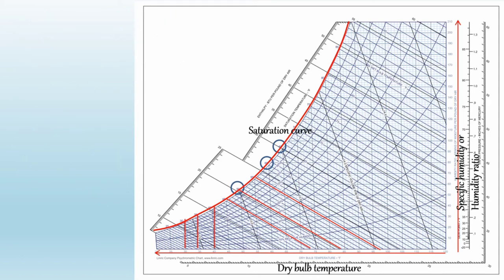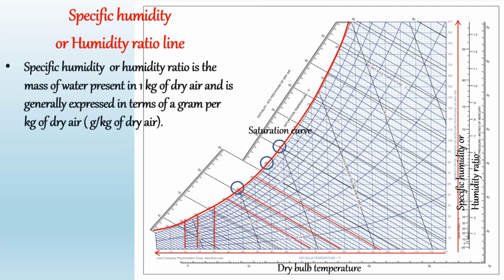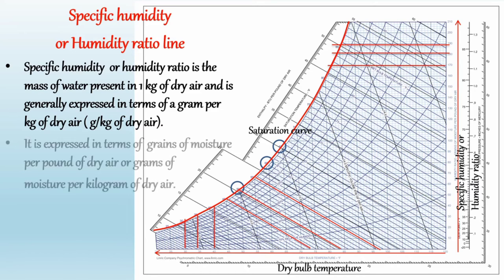The next line is the specific humidity or humidity ratio line. Humidity ratio, or specific humidity, is the mass of water present in 1 kilogram of dry air, and is generally expressed in grams per kilogram of dry air. In the psychrometric chart, the specific humidity lines are horizontal — parallel to the x-axis up to the saturation curve — and are uniformly spaced. It is expressed in terms of grains of moisture per pound of dry air, or grams of moisture per kilogram of dry air.